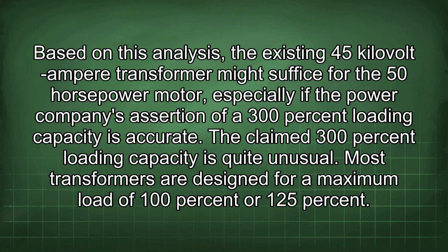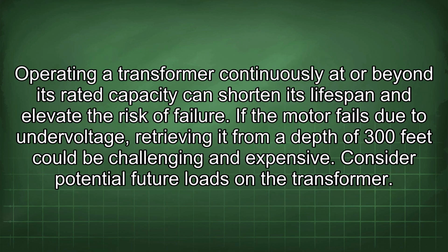The claimed 300% loading capacity is quite unusual. Most transformers are designed for a maximum load of 100% or 125%. Operating a transformer continuously at or beyond its rated capacity can shorten its lifespan and elevate the risk of failure. If the motor fails due to undervoltage, retrieving it from a depth of 300 feet could be challenging and expensive.